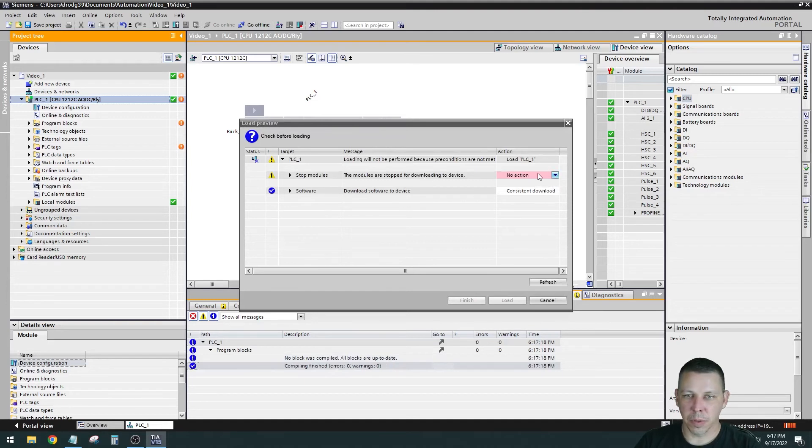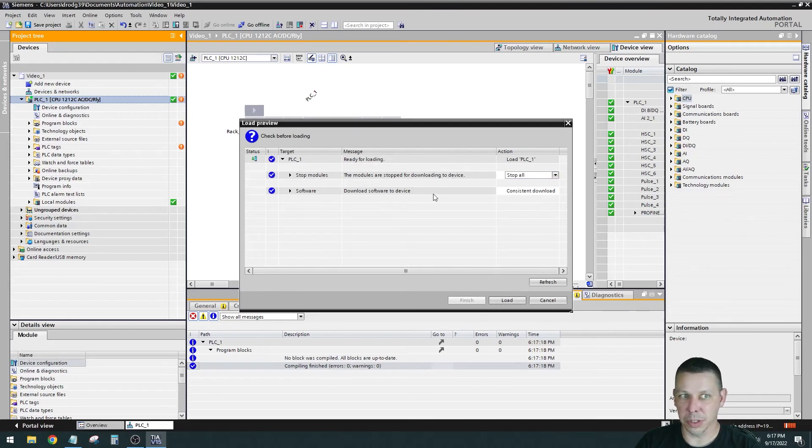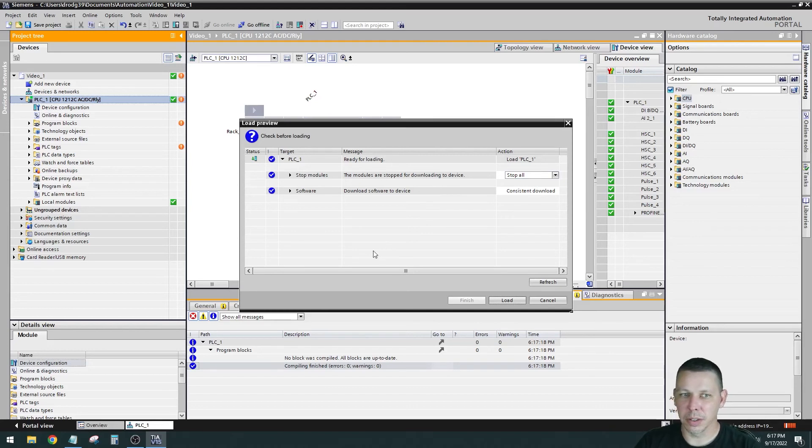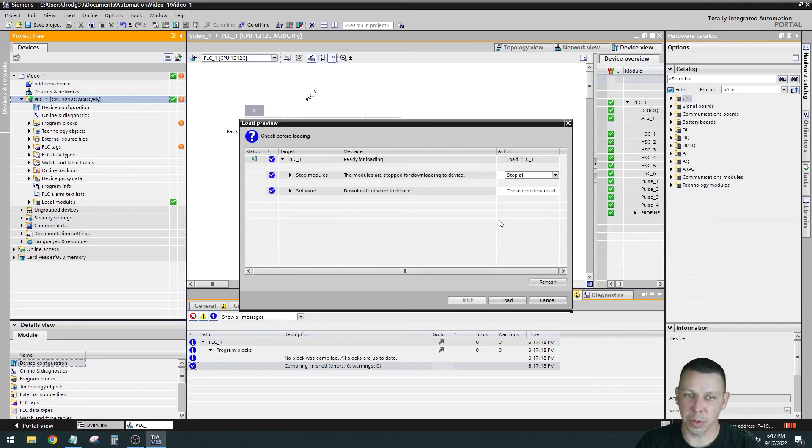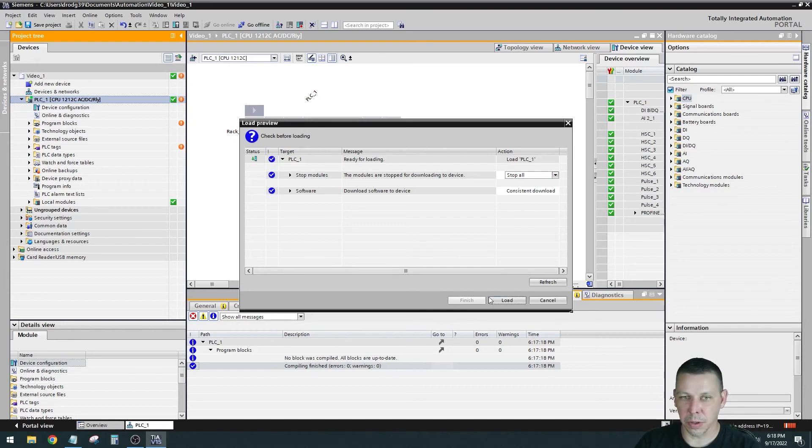Now I'm going to download all the software to the processor. If you see a red, it means you have to do something or it's not going to work. So you go stop all. It's saying, do I want to stop all the modules, all the IO modules while I load this logic into it. You have to hit - it has a warning - you have to stop all because what if some of those modules are controlling something that's currently running? I don't have this PLC connected to any piece of machinery, but most of the time it will be connected to a piece of machinery. Some of the stuff that you're stopping might be needed to run for safety or for whatever reason. So that's why it's in red. Now I'm going to hit load.